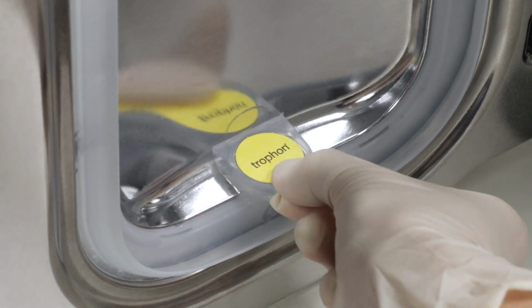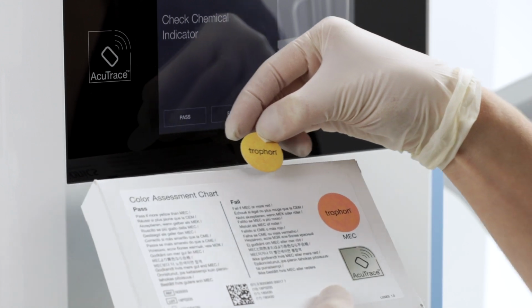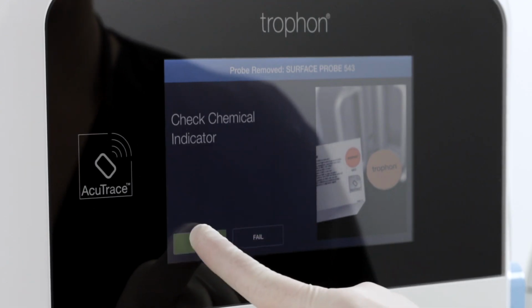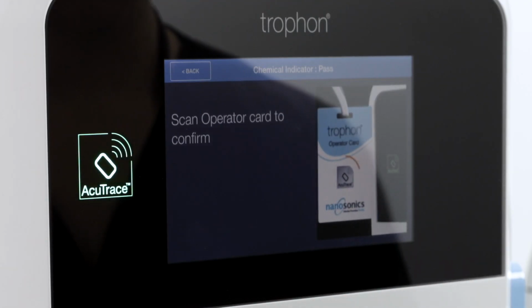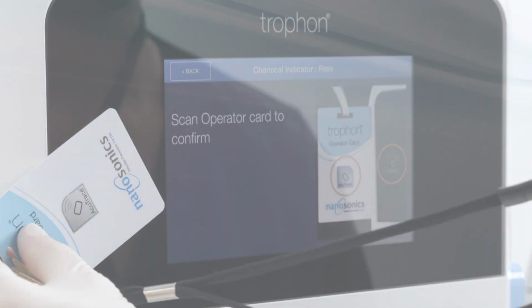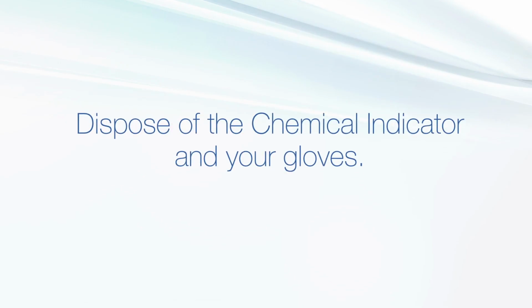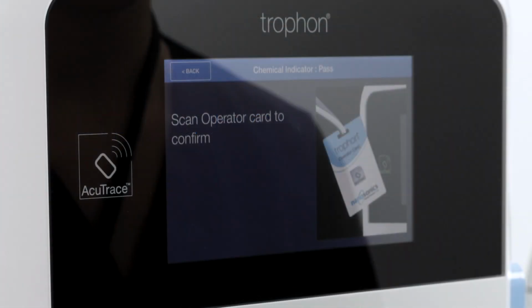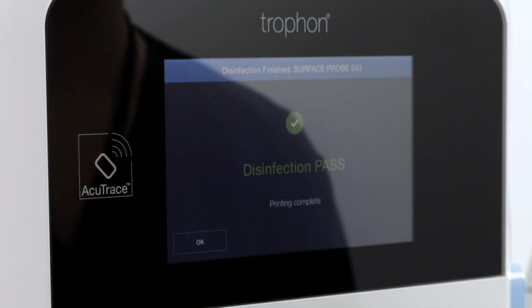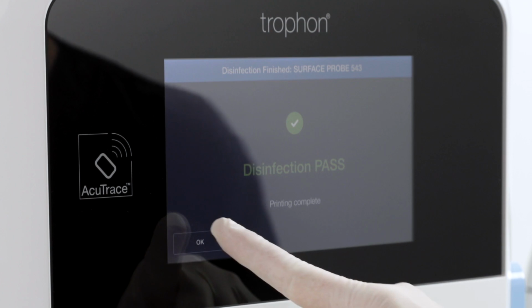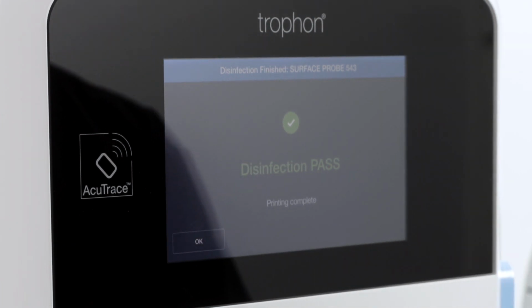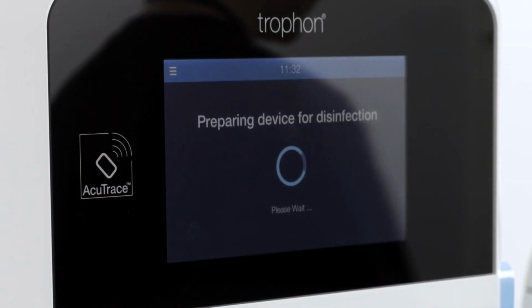Check the chemical indicator pass status using the color assessment chart. Verify the chemical indicator pass and scan your operator card. Dispose of the chemical indicator and your gloves. The disinfection cycle is now complete and the result is shown on the screen. Press OK and trophon2 will be ready for your next disinfection cycle.